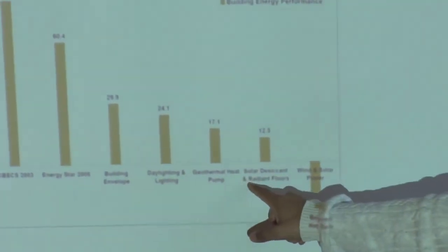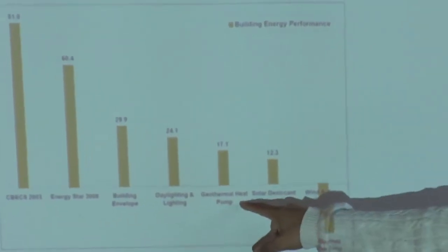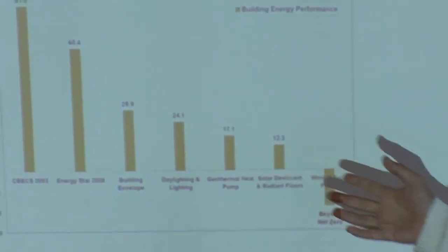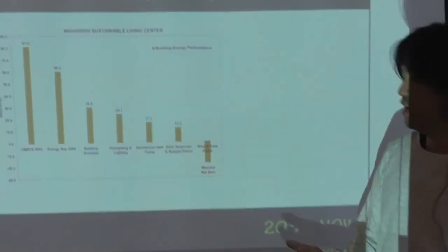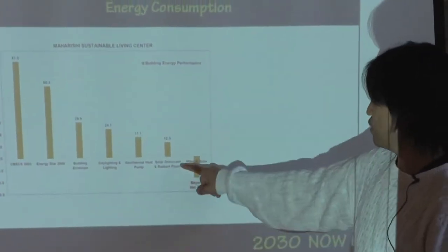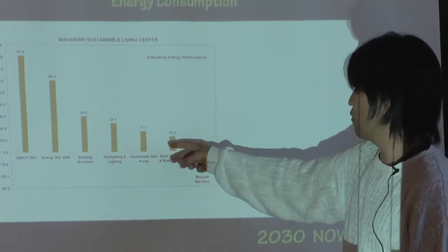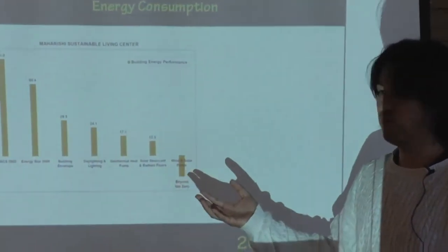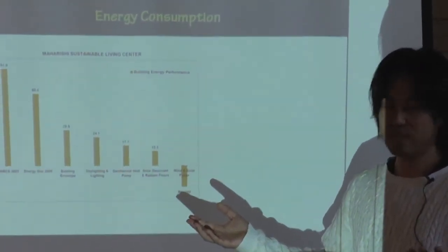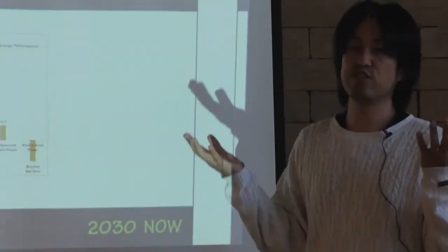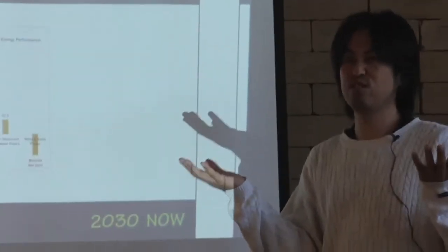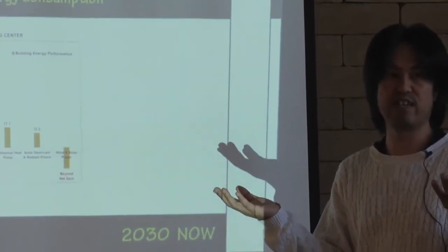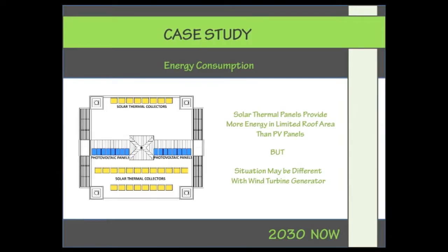And then I just put in, for comparison purposes, a geothermal heat pump. You can come down to 17 kBTU per square foot per year energy use with a geothermal heat pump. But compared to our solar desiccant and radiant floor system, there is a 5 kBTU difference, which we have to compensate with PV panels. So that's why we are using a solar thermal system, because we can use less surface area on the roof. If we try to do it with just PV, we may not have enough roof area just for PV. But fortunately we have wind, so maybe with more wind it's not going to be an issue. But if you're going to just do a net zero building with PV, you've got to be careful with the available roof surface area.